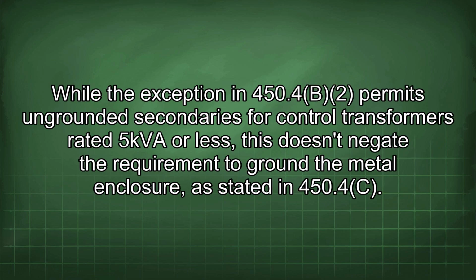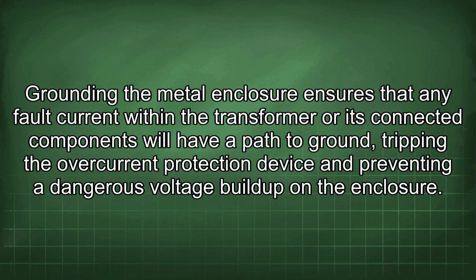While the exception in 450.4(B)(2) permits ungrounded secondaries for control transformers rated 5kVA or less, this doesn't negate the requirement to ground the metal enclosure, as stated in 450.4(C). Grounding the metal enclosure ensures that any fault current within the transformer or its connected components will have a path to ground, tripping the overcurrent protection device and preventing a dangerous voltage buildup on the enclosure.